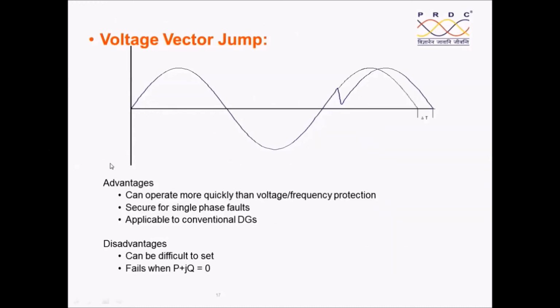This is what we call voltage vector jump. The advantage is that it can operate more quickly than the voltage or frequency protection because it is without any time delay. I cannot have an under voltage or under frequency function without a time delay. But this voltage vector jump happens whenever the grid is lost. Immediately there is a voltage vector jump. Therefore, without any time delay, we will be able to implement this voltage vector shift relay functionality.